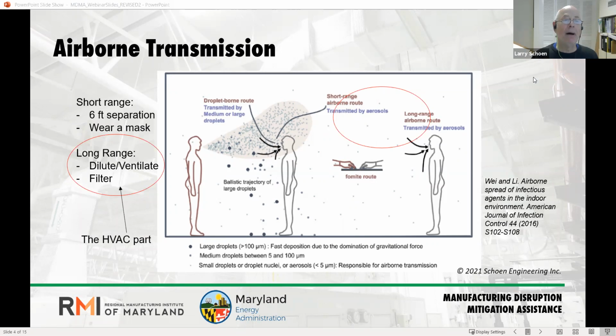This 6 feet came from a rounding of 2 meters, which actually rounds to 7 feet, because 1 meter was found to be the range at which a lot of the larger droplets fall. 6 feet is very arbitrary. So the thing is not to have close contact and wear a mask. That's the behavioral level. We really cannot affect that with an HVAC system, regardless of what anybody's claiming about good ventilation, filtration, adding substances to the air. There is really not good evidence that any of that can affect the short range.